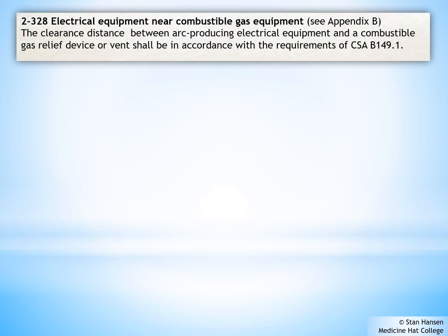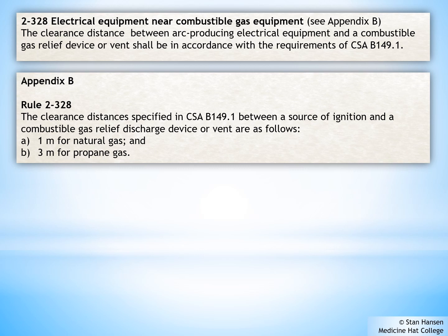When it comes to the disconnect switching for an AC unit, I have to make sure I pay attention to Rule 2-328, electrical equipment near combustible gas equipment. So if you think about our gas meter on the side of our house, where we place the disconnect switch for my air conditioner is going to matter. We need to make sure that we look at Appendix B, which states that we must have a minimum of a 1 meter distance for natural gas relief valves or 3 meters if we're dealing with a propane gas system. So make sure you know what type of gas the house has and make sure that your AC disconnect is far enough away from that gas meter. It's not going to cause any problems.